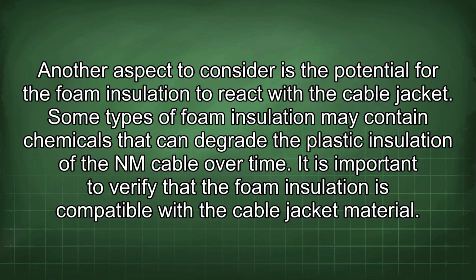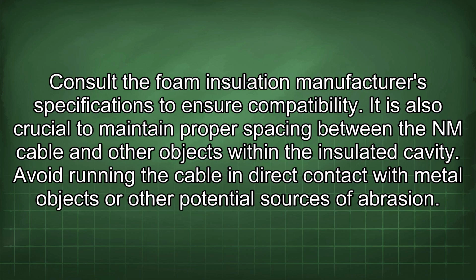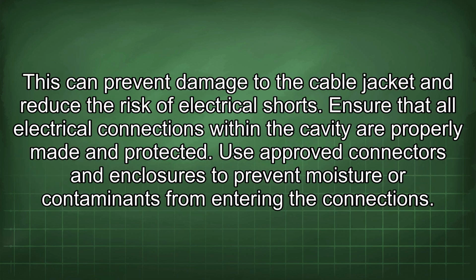Another aspect to consider is the potential for the foam insulation to react with the cable jacket. Some types of foam insulation may contain chemicals that can degrade the plastic insulation of the NM cable over time. It is important to verify that the foam insulation is compatible with the cable jacket material. Consult the foam insulation manufacturer's specifications to ensure compatibility. It is also crucial to maintain proper spacing between the NM cable and other objects within the insulated cavity. Avoid running the cable in direct contact with metal objects or other potential sources of abrasion. This can prevent damage to the cable jacket and reduce the risk of electrical shorts.